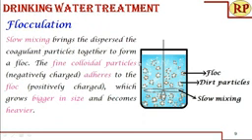Why we reduce the speed of stirring here is mainly so that the coagulant particles come closer. That is, the dispersed particles from the coagulation step come closer when the mixing speed is reduced. This forms a floc. This is positively charged, and mostly the fine colloidal particles are negatively charged. So the negatively charged particles come closer to the positively charged flocs and get adsorbed, and neutral particles like dirt particles also adhere around the floc.